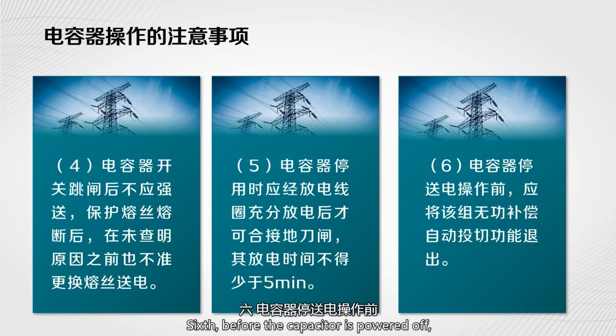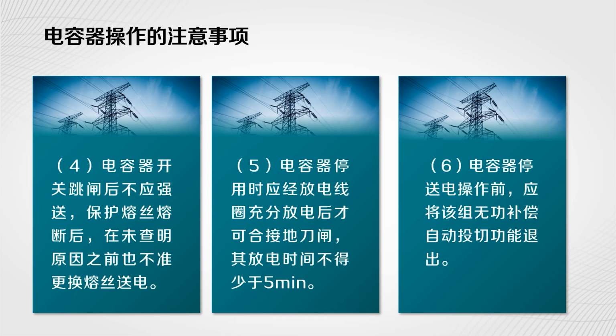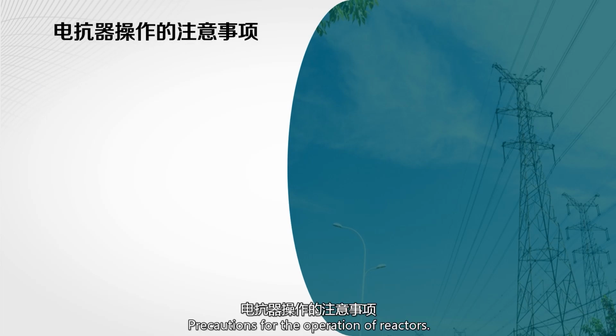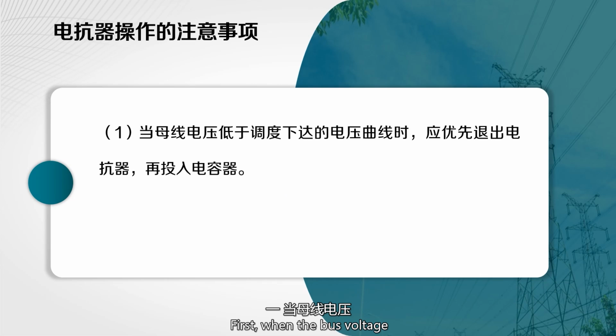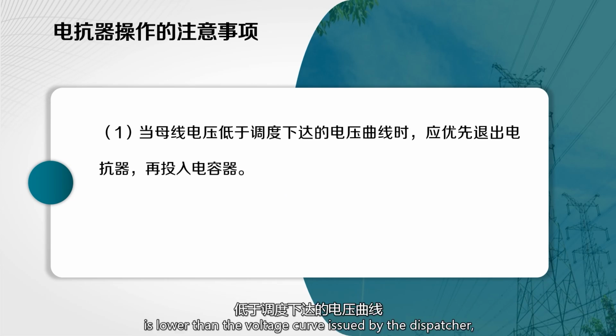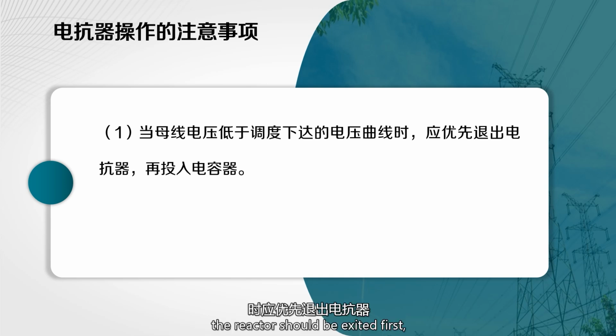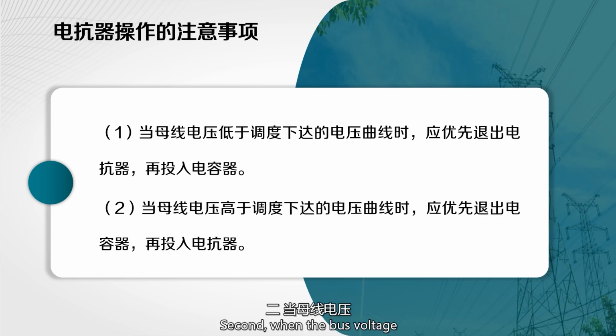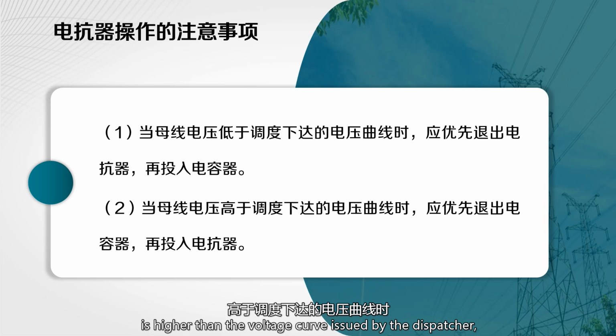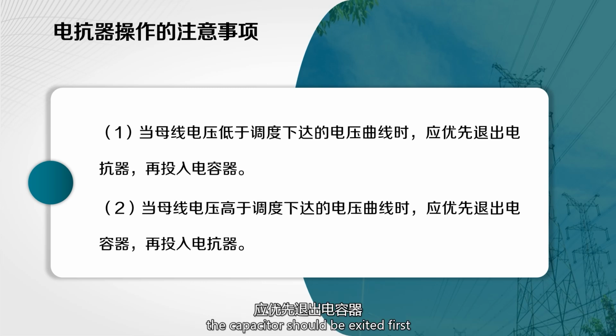Sixth, before the capacitor is powered off, the automatic switching function of the group of reactive power compensation should be withdrawn. Precautions for the operation of reactors. First, when the bus voltage is lower than the voltage curve issued by the dispatcher, the reactor should exit first, and then the capacitor should be put in. Second, when the bus voltage is higher than the voltage curve issued by the dispatcher, the capacitor should exit first, and then the reactor should be put in.